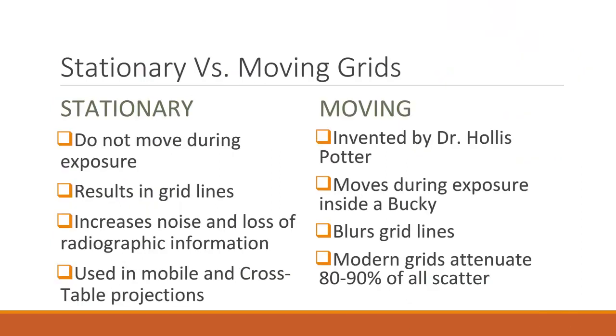There are many variations in grids. Some grids are stationary and do not move. Because of this, the lead foil strips, although quite small, can be slightly seen on the resulting radiograph. The visualization of the strips is considered noise on our image and is undesirable because there is a slight loss of radiographic information in the areas where the lead strips absorbed non-scattered x-rays. These types of grids are utilized for mobile radiography and performing cross-table lateral projections, as well as unconventional projections such as those required by some trauma situations.